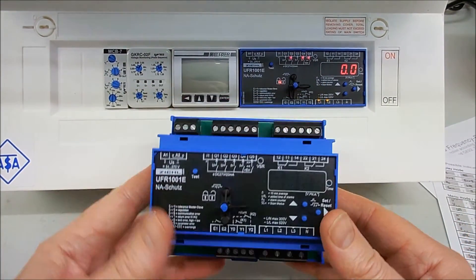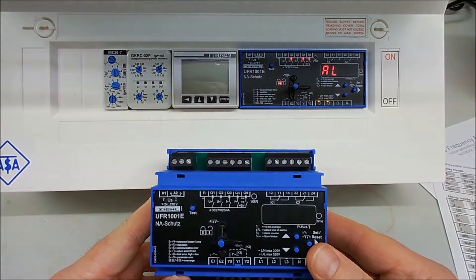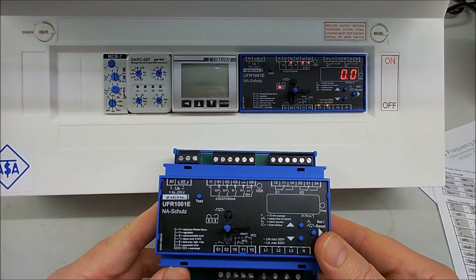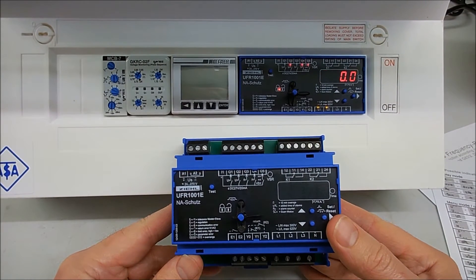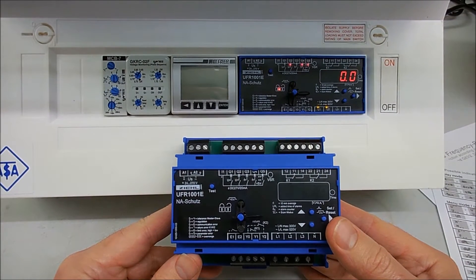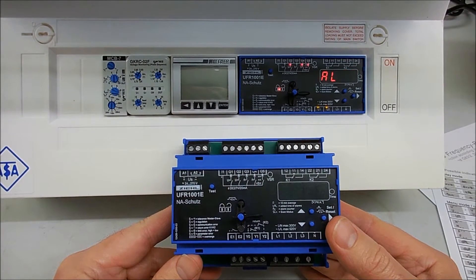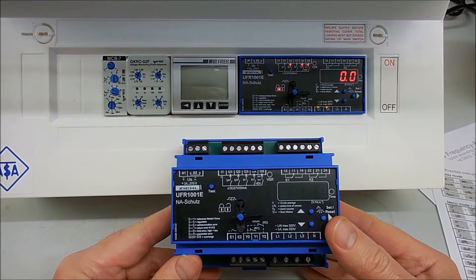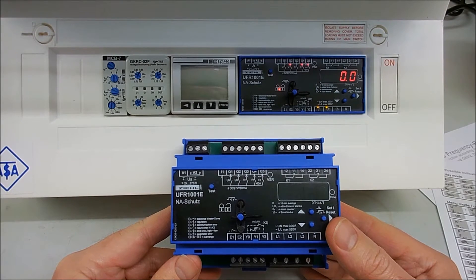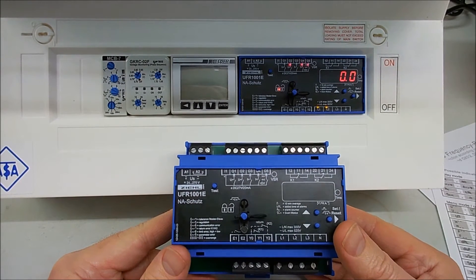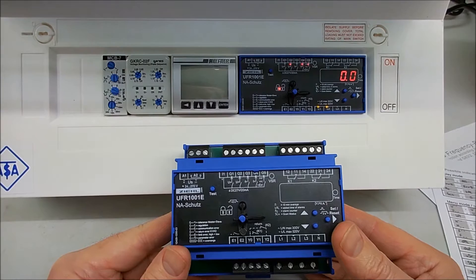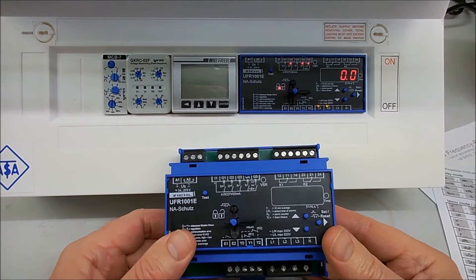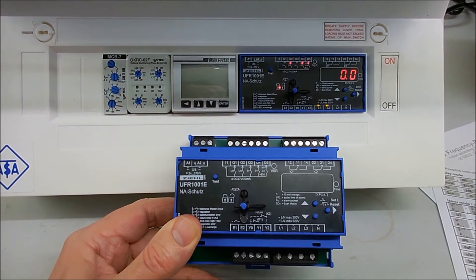The unit itself is used for monitoring under and over voltage at both levels, under and over frequency at both levels, vector shift and ROCOF. All of those values can be either turned off or turned on.